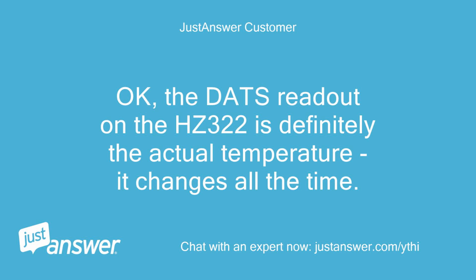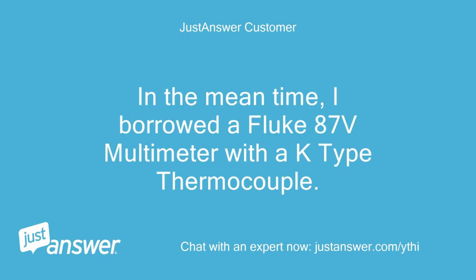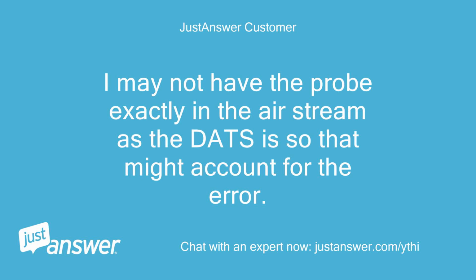Okay, the DATS readout on the HZ322 is definitely the actual temperature. It changes all the time. Not a set point. In the meantime, I borrowed a Fluke 87V multimeter with a K-type thermocouple. The current DATS readout is about 2 to 3 degrees lower than the Fluke. I may not have the probe exactly in the air stream as the DATS is, so that might account for the error.